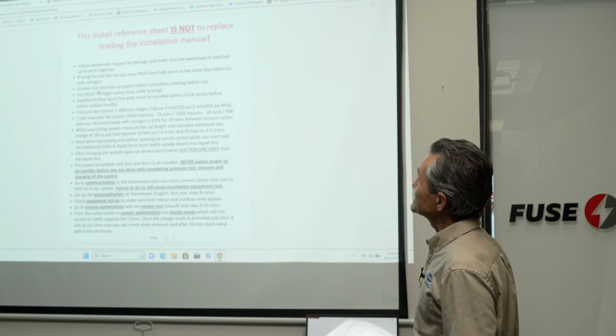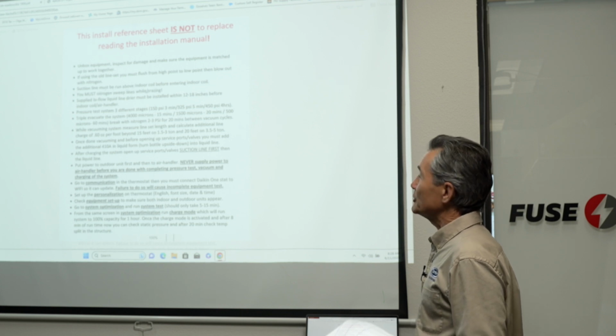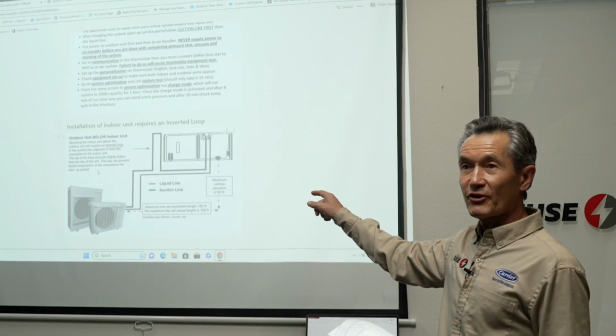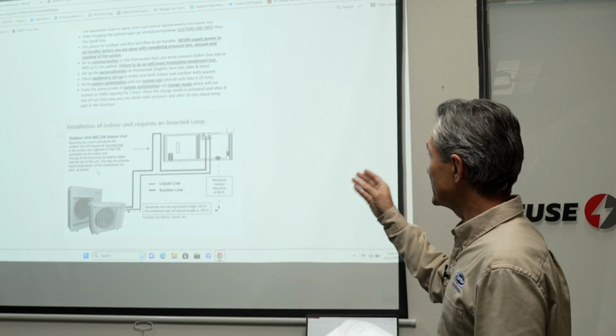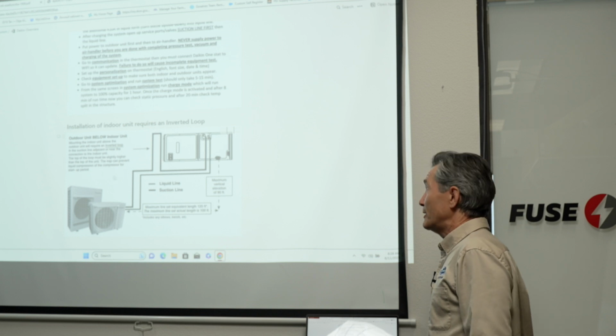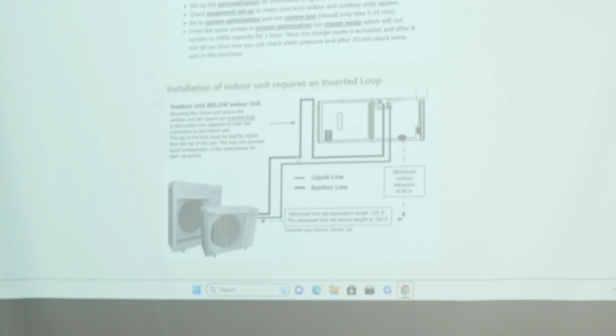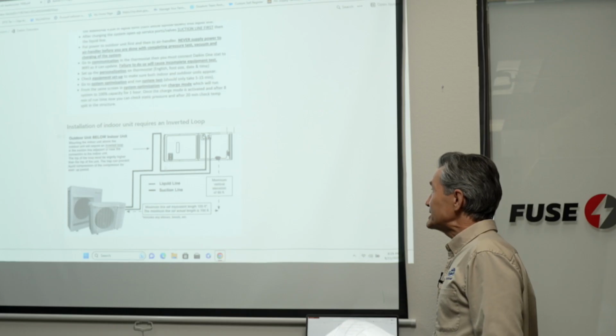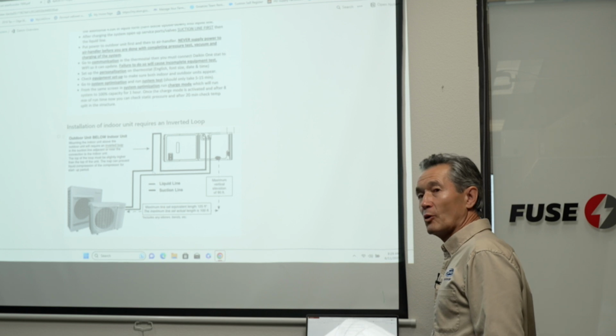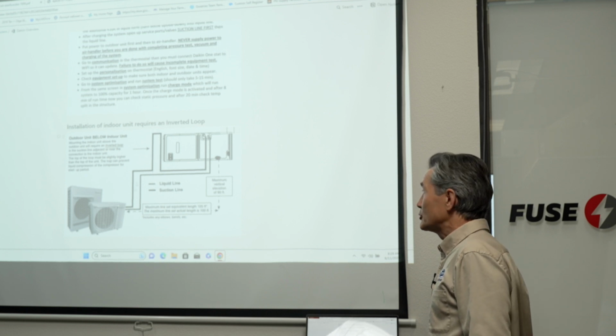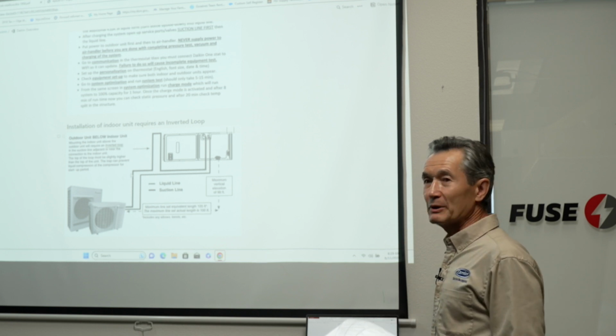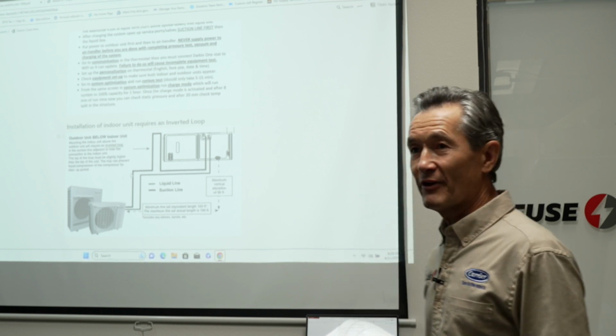This is another good point. Number 3, suction line must be run above the indoor coil. I've got a picture of that. Let's go and have a look. This is in the specification or installation manual. Are you guys doing it or not? I'm not sure, but there is a reason for that. The suction line is in the picture, the thicker line. It should be, it says, slightly higher above the top of the indoor unit. This loop will help keep certain oil in the refrigerant from going back to the compressor and avoid a potential hammering effect. So that's why during the installation you really have to keep that in mind.